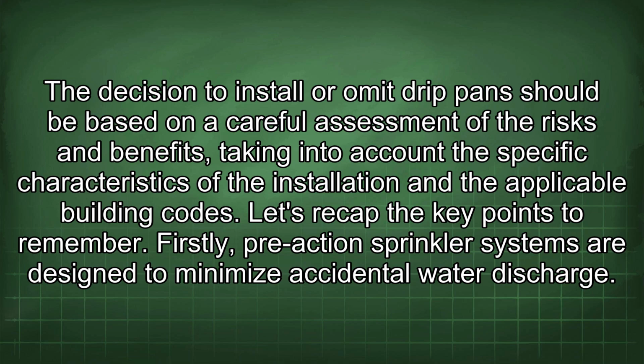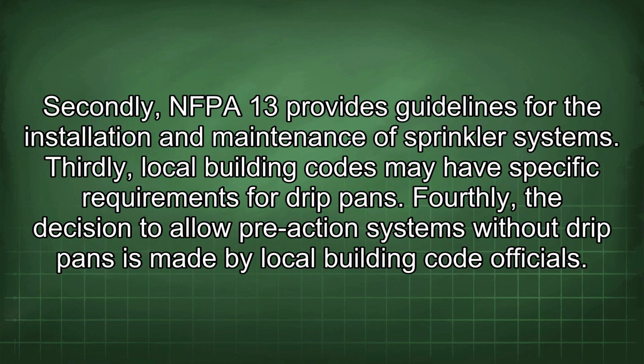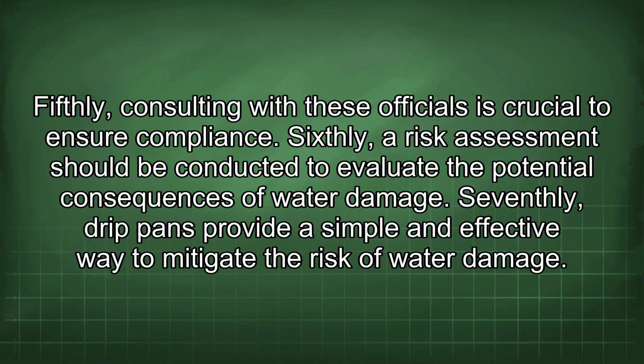Let's recap the key points to remember. Firstly, pre-action sprinkler systems are designed to minimize accidental water discharge. Secondly, NFPA 13 provides guidelines for the installation and maintenance of sprinkler systems. Thirdly, local building codes may have specific requirements for drip pans. Fourthly, the decision to allow pre-action systems without drip pans is made by local building code officials. Fifthly, consulting with these officials is crucial to ensure compliance. Sixthly, a risk assessment should be conducted to evaluate the potential consequences of water damage. Seventhly, drip pans provide a simple and effective way to mitigate the risk of water damage.